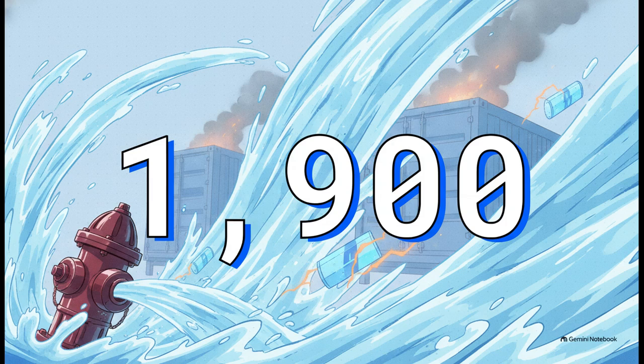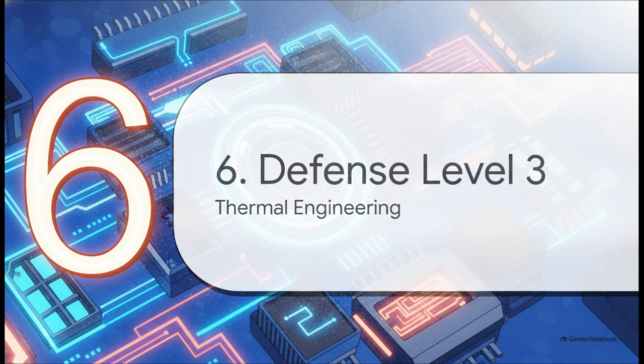1,900. That is the bare minimum number of liters of water per minute that an external hydrant has to supply for at least 2 solid hours to properly control a BESS fire. To put that into perspective for you, that is like emptying a large hot tub directly onto the fire every single minute. This massive water requirement just highlights how insanely intense and stubborn these chemical fires are. Without that sustained, huge volume of water, cooling the core down enough to stop it from just reigniting again is practically impossible. Finally, we reach Section 6, Defense Level 3, Engineering.